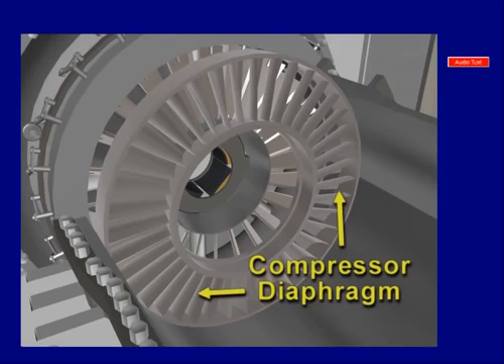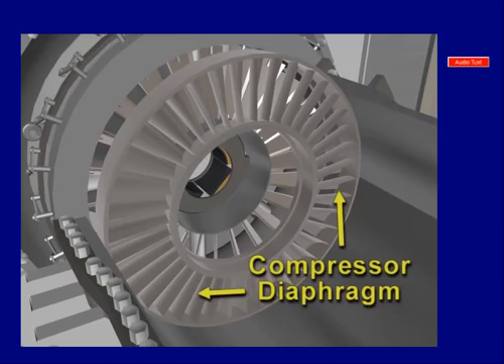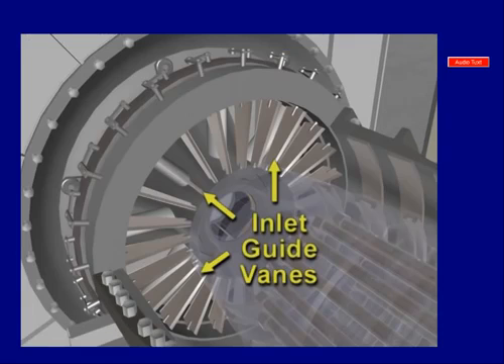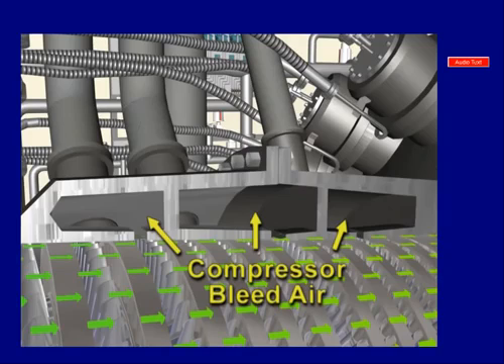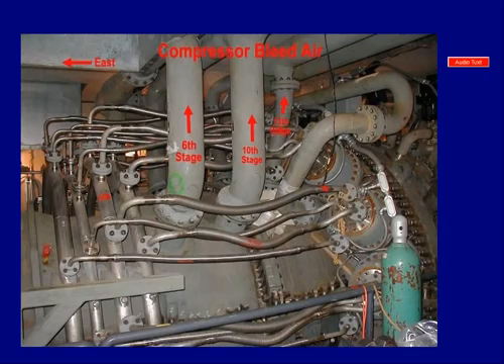Dovetail blade roots attach the blades to the rotor shaft. The compressor diaphragm has stationary airfoil-shaped vanes mounted in semicircular rings set into the compressor housing. Through the use of variable inlet guide vanes and compressor stage bleed valves, the compressor bleed air system controls the amount of air flowing in the compressor section to prevent pressure surging or blade stalling.